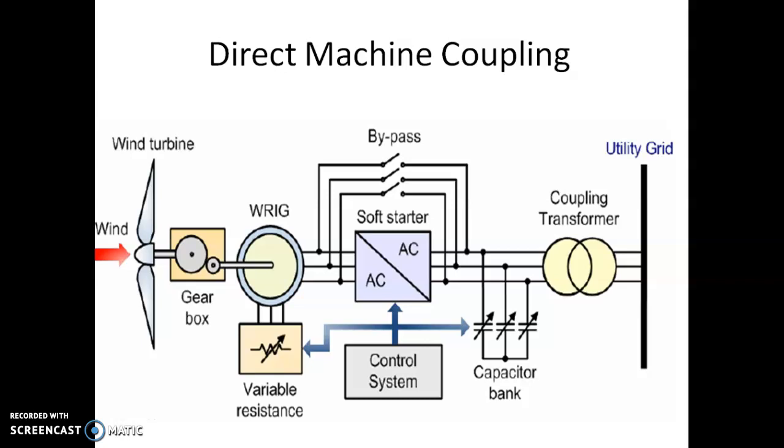A synchronous generator can be a source of both active and reactive power to the electrical system. An induction machine is used to interface variable speed energy sources with the grid. But there are some disadvantages: it draws reactive power from the system, and it also draws a very high starting current that may cause voltage or local flickering. Due to that, we use a capacitor bank to reduce it.